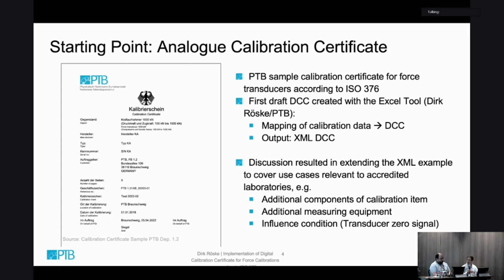The first draft we created with an Excel tool that was made by a colleague also at PTB. This stores all the data from the calibration automatically into an Excel sheet. And then he developed a program that can make the digital calibration certificate out of that data. Then you can store an XML file directly from your measurement data.